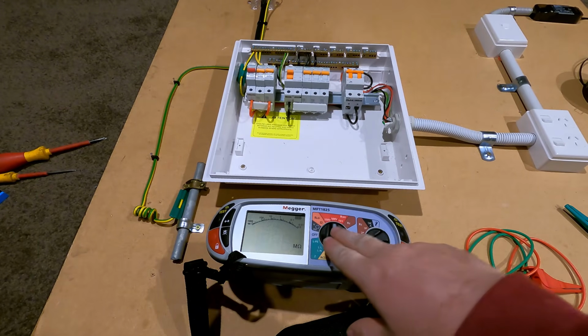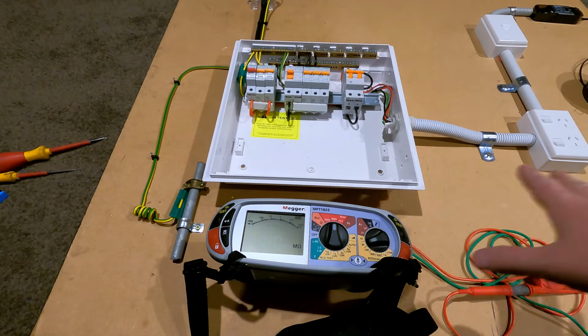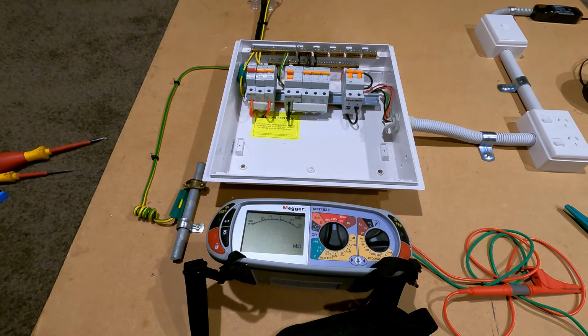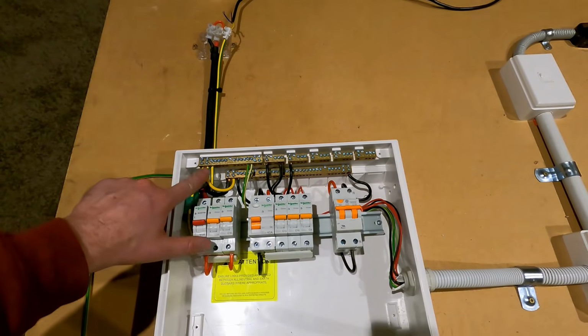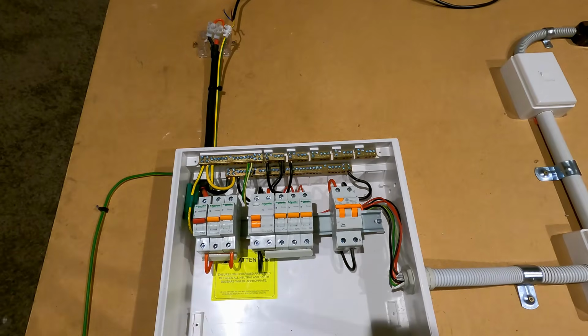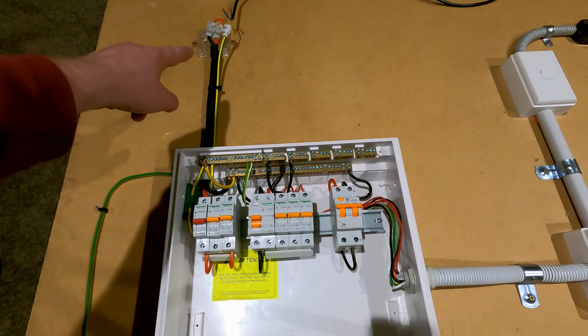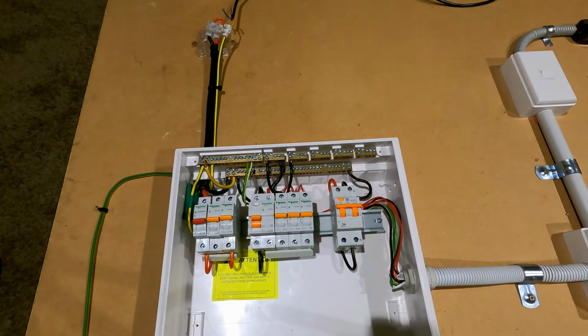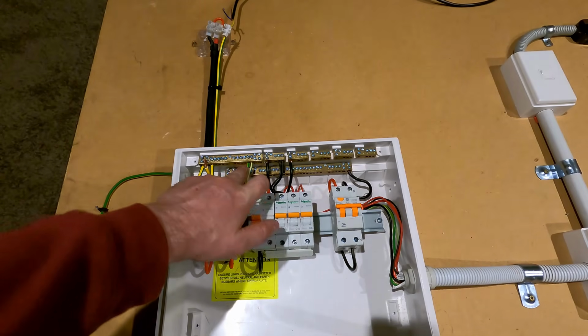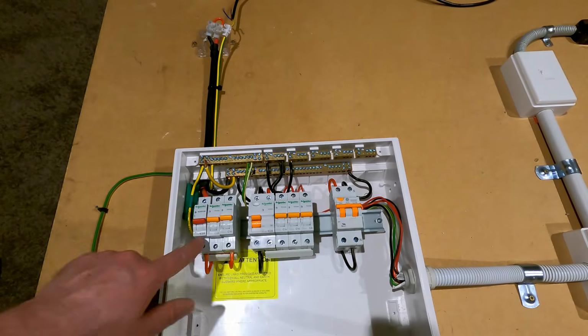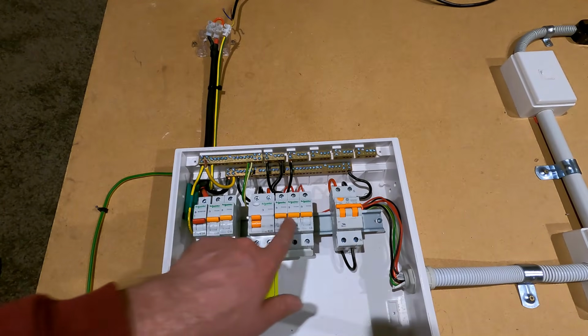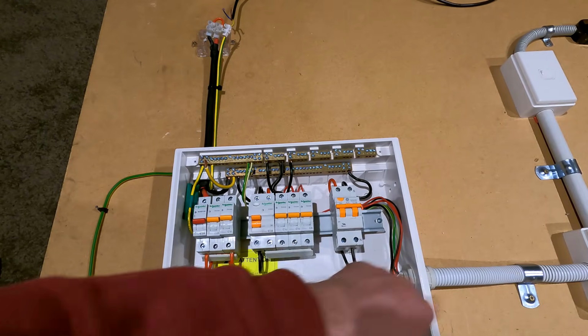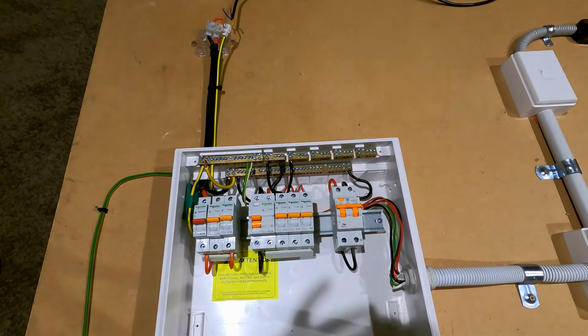Just keep in mind that if you're throwing 500 volts DC down the load side of the circuits, there is some electrical equipment that can get fried, such as dimmers and some alarm systems. So make sure you disconnect those before doing this test. Now the next thing we do is we get rid of this MEN link, just unplug it for now, because now that we've shorted out the phase and the neutral on the line side, we've got a complete circuit between the neutral bar all the way through all of the phases and through all of these breakers and RCDs, all the way out to the complete loads on the circuits.